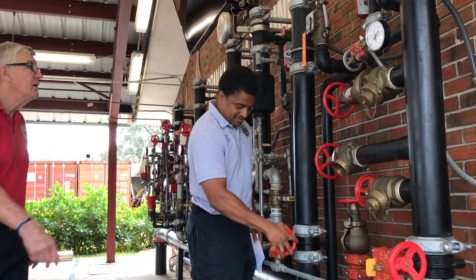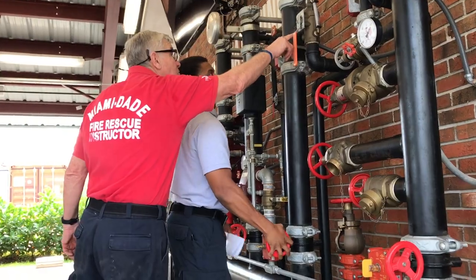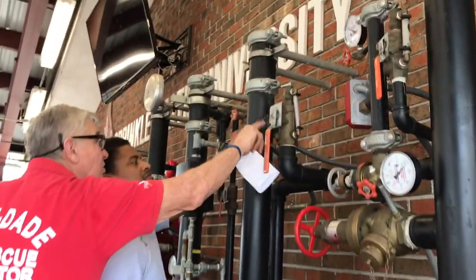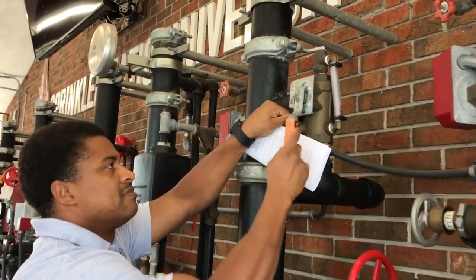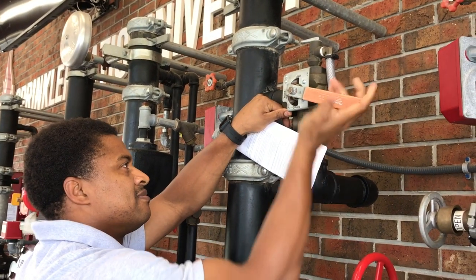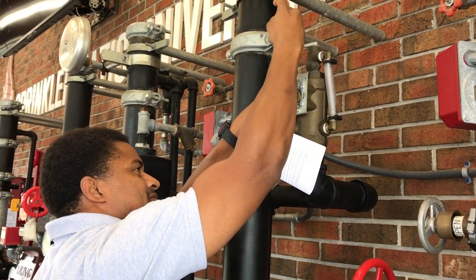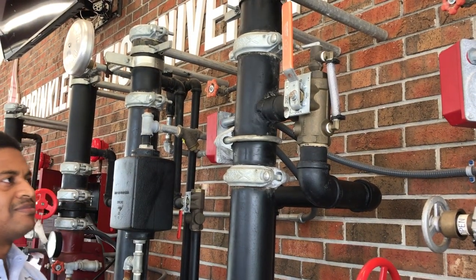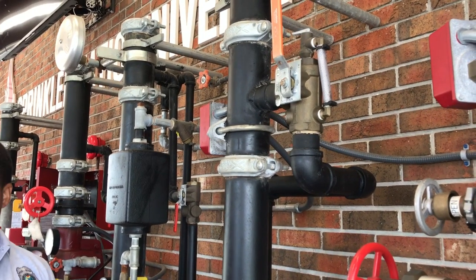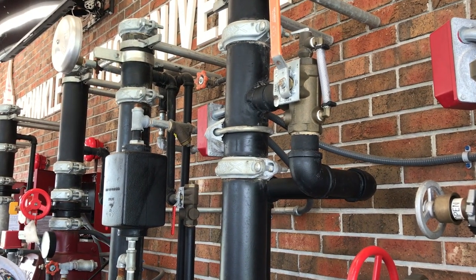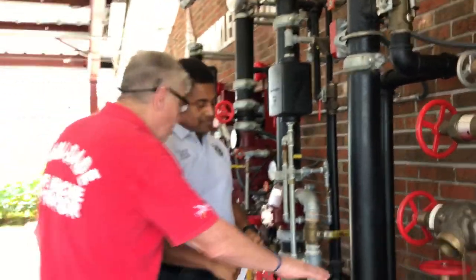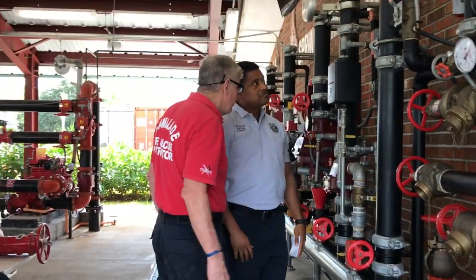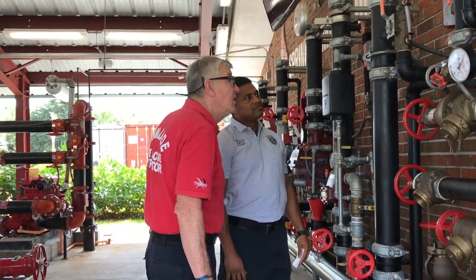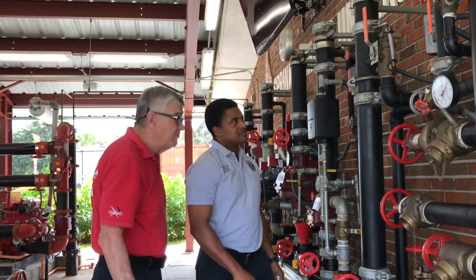Okay, Mark, now press that little button and let's move the lever to drain. All the way to drain. All right. Brother, we have effectively shut off the sprinkler system. We've drained the water that's trapped between the closed valve and the activated sprinkler head. So Mark, go ahead and close it.